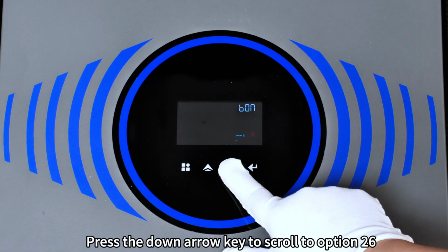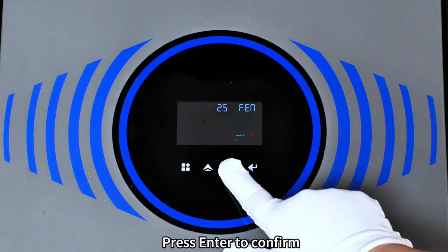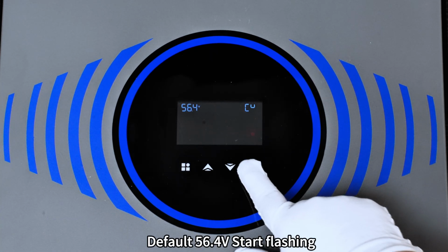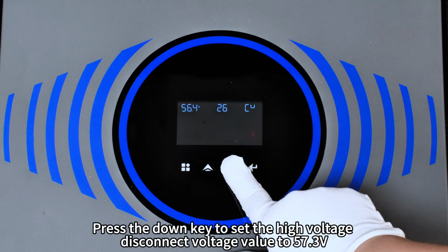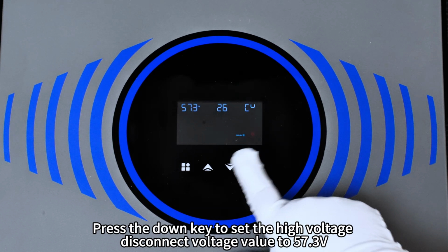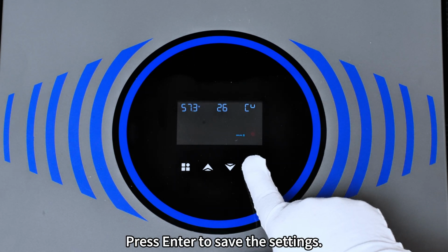Press the down arrow key to scroll to option 26. Press Enter to confirm. The default is 56.4V and it starts flashing. Press the down key to set the high voltage. Set the disconnect voltage value to 57.3V. Press Enter to save the settings.